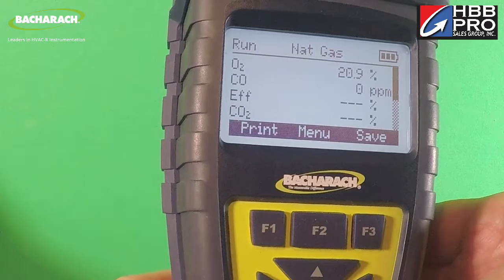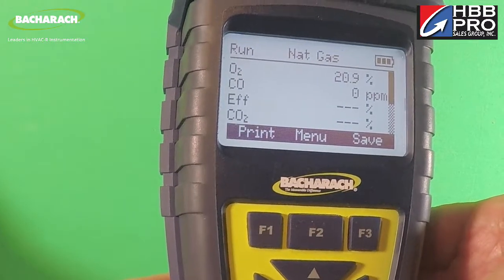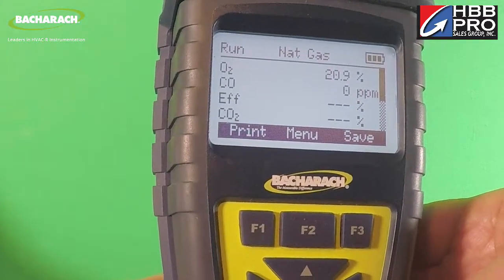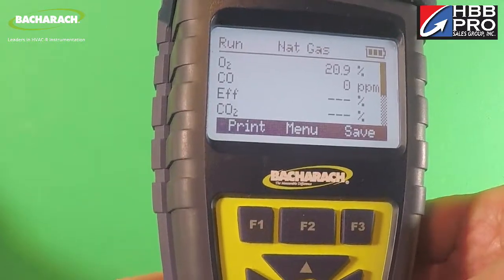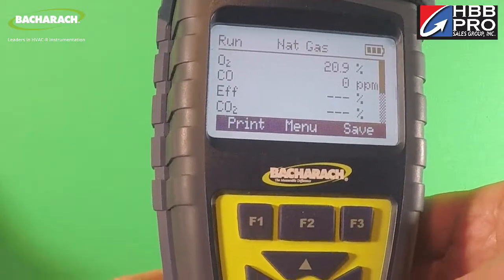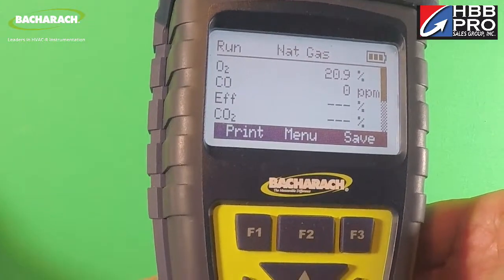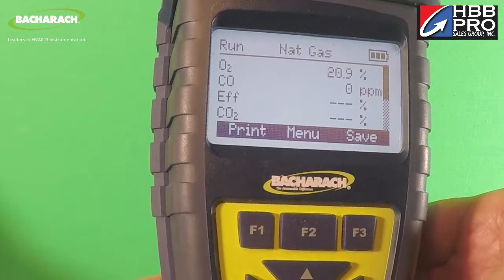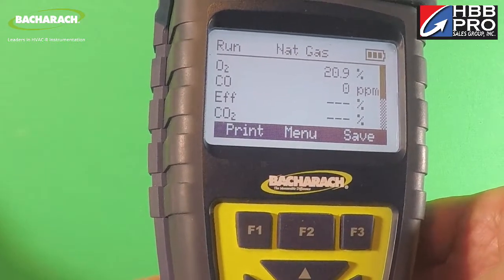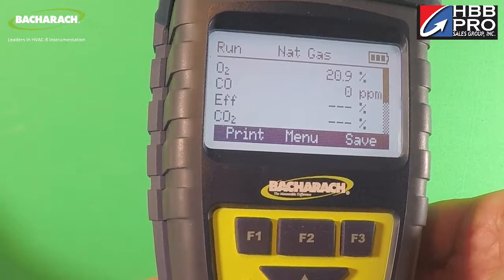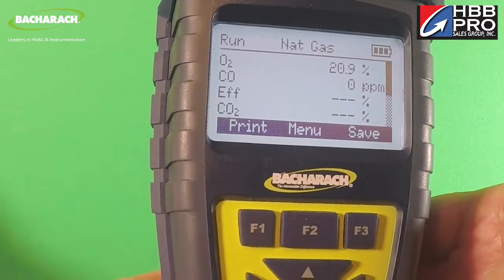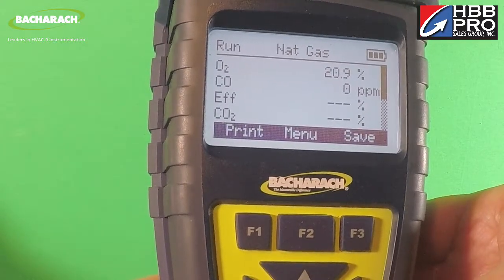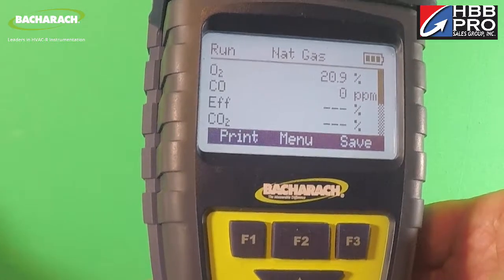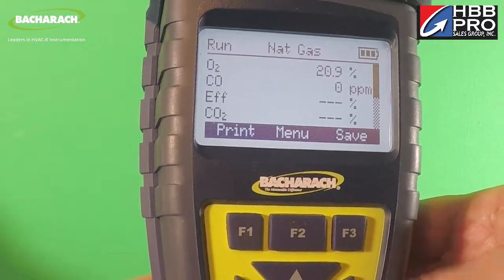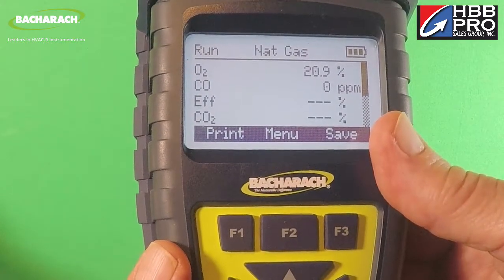There you'll find a PDF file entitled Carbon Monoxide Combustion Testing Seminar Handout that will show where to test on different types of equipment, and it'll also give you some rules of thumb on what kinds of readings are generally considered acceptable. Always check with the manufacturer to verify what readings their equipment is designed and engineered to operate at. And a lot of times, a lot of manufacturers are starting to include that information right in their manual.